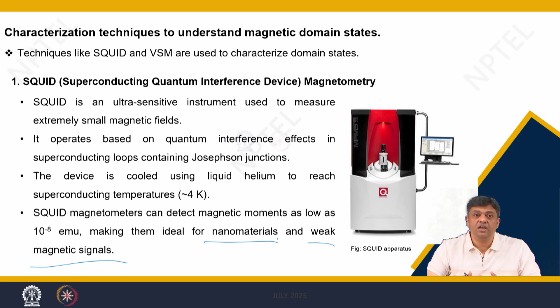How do you perform such measurements? They are very simple measurements. The whole setup may be an expensive setup, but the operation is not very difficult. Once you learn it, you can easily do it, there is no problem in that. So, you have to take a sample and place it in a uniform magnetic field, and it is moved through superconducting detection coils. Now, as the sample moves, what happens? It induces a current in the coil that is detected by the changes in the magnetic flux. Now, the change in the flux is converted to a voltage signal, which is directly proportional to the magnetic moment of the sample. So, the higher the voltage signal, the higher the magnetic moment.